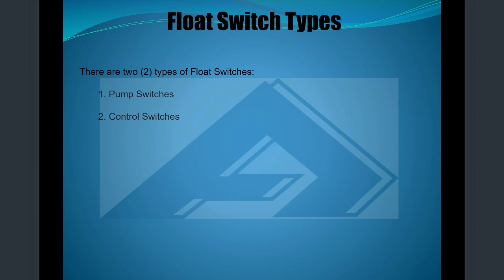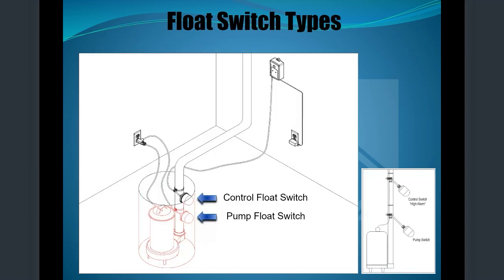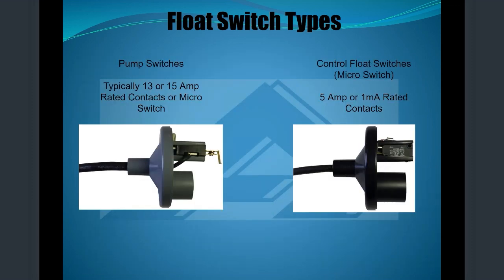So next. So pump and control switches next. So this is like a sump pit model or a diagram. You have your pump float on the bottom and your control switch up top. Your control float would be connected to an indoor alarm. So that's more low amps, like up to 5 amps for that. And then your pump float carries a full load amps of your pump up to 15 amps with our current floats. And you'll see on the left there's a piggyback. It's piggybacked in series with your pump into the receptacle. So next.